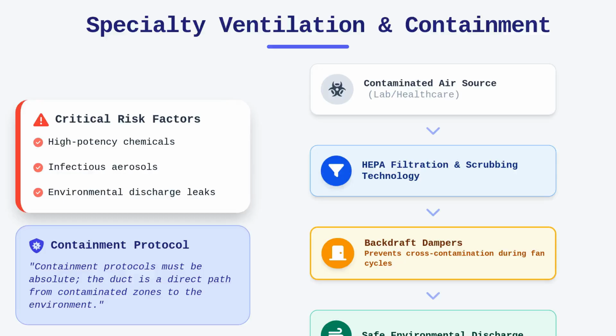You must verify the integrity of the exhaust path, ensuring that backdraft dampers are functioning correctly to prevent cross-contamination when fans cycle off. If these dampers do not seal properly, contaminated air from one lab sequence could migrate to another area, completely undermining the engineering controls that the facility relies upon for occupant safety.